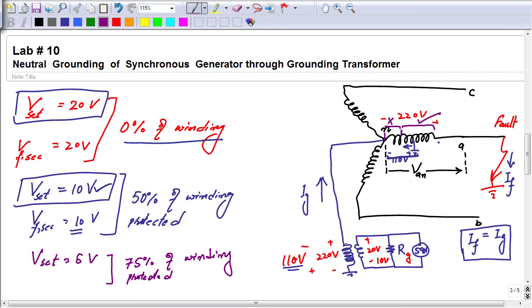When there is no fault, that will be due to third harmonic, due to unbalance in the load, and due to unbalance in the supply. So there will be a zero sequence current that would exist even if the system is in perfectly normal condition. That's why we will have to set the pickup setting of this voltage relay to some non-zero value. This non-zero value will make some portion of this winding unprotected by this protection. This is the main theme.